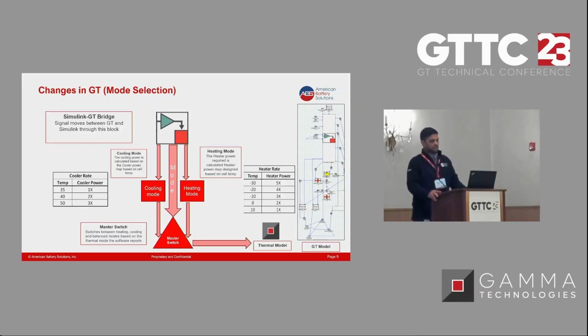We calculate both the cooling rate and the heating rate in parallel, based on the tables shown here. Based on the temperature, the cooler power either increases or decreases, and based on the cell temperature, the heater rate increases or decreases. This table covers a wide range of temperatures based on the application. All three pieces of information, the cooling rate, heating rate, and mode, go to the master switch, which decides which signal to pass on based on the thermal mode. On the right is a visual representation of how the logic was implemented in GT Suite.